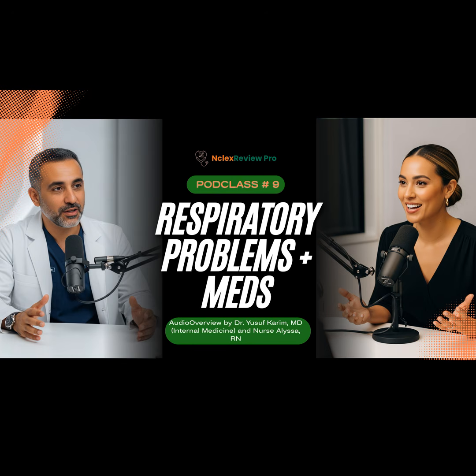Managing pressures is also the fundamental challenge of mechanical ventilation. Ventilators monitor airway resistance and compliance through specific alarms. A high-pressure alarm indicates the machine is encountering increased resistance during the inspiratory phase. This suggests acute bronchospasm, a mucus plug occluding the tube, or the patient actively biting the tube. Conversely, a low-pressure alarm means the ventilator is delivering tidal volume but encountering zero resistance. The air is escaping the closed circuit, almost universally indicating a disconnection in the ventilator tubing or a deflated endotracheal tube cuff.